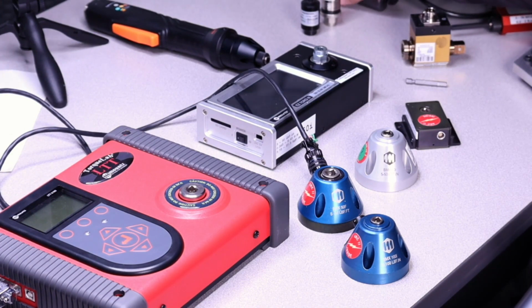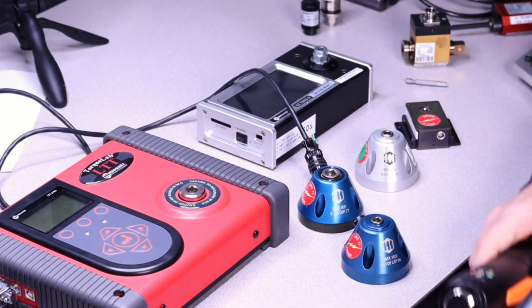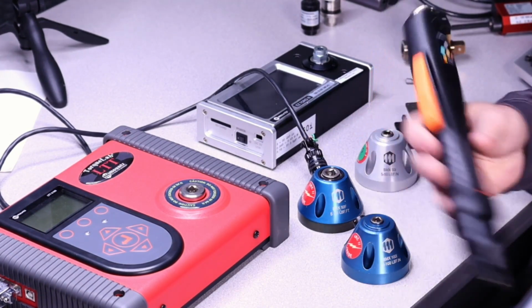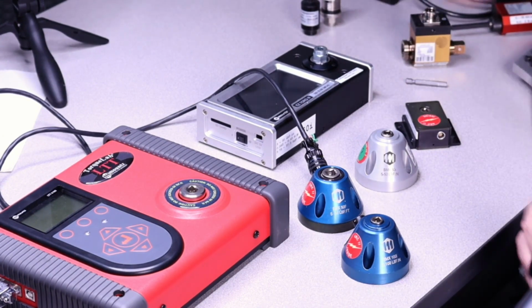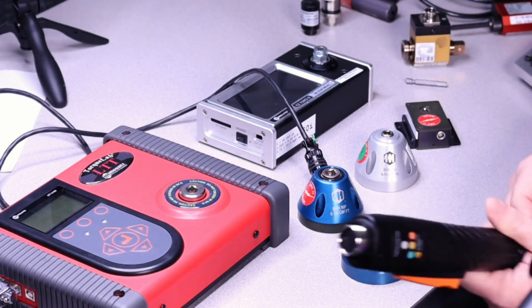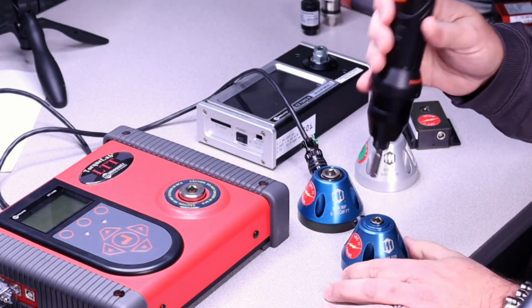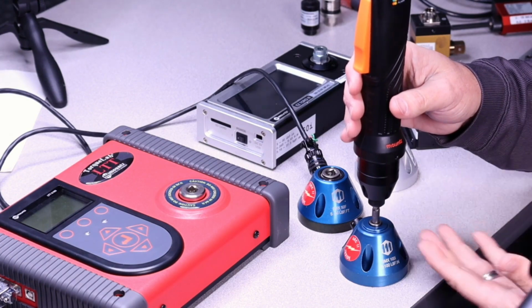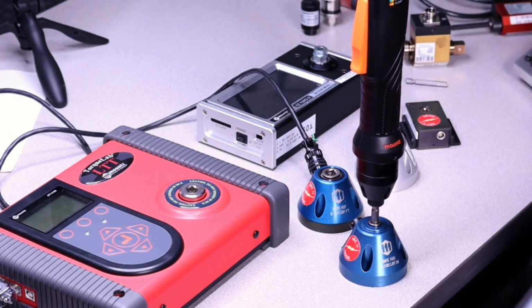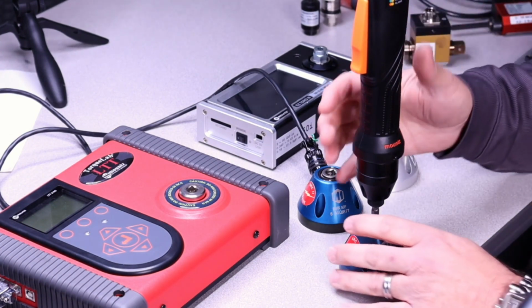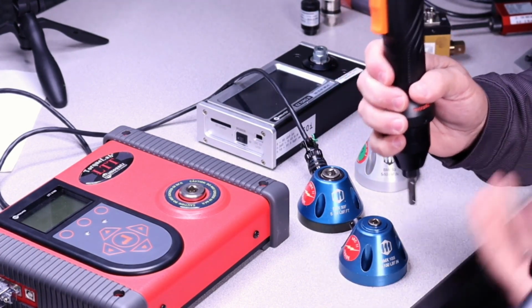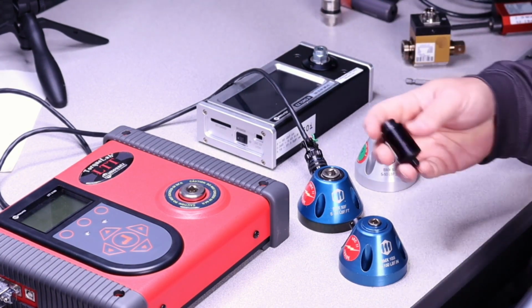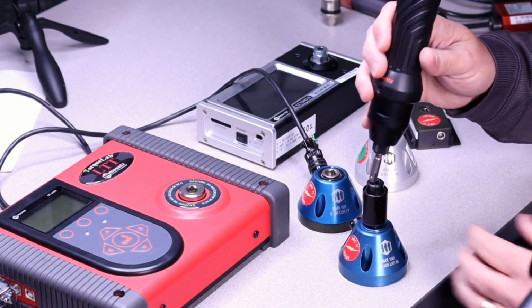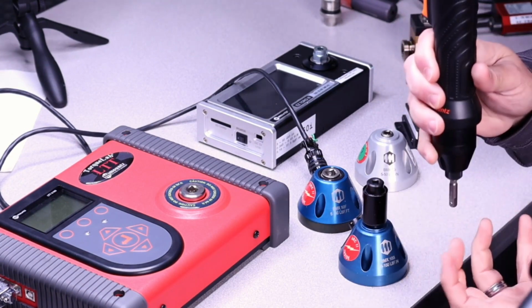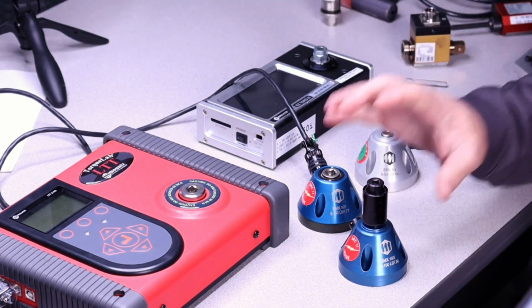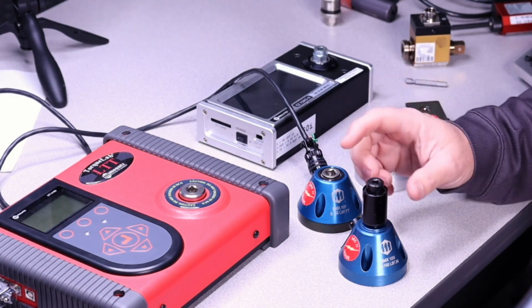We can also do the same with a power tool, using pneumatic power tools, electric clutch tools, or DC type tools. The requirement is that we cannot take a power tool and go directly into the sensor itself, because this won't give an accurate reading of the torque output since we're not allowing the tool to ramp up to its running RPM during fastening. To solve this, we use what's called a rundown adapter or joint simulator, which allows the tool to come up to its RPM and then clutch or stop when the threaded portion of the rundown or joint simulator is met.